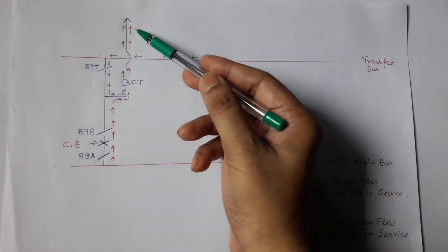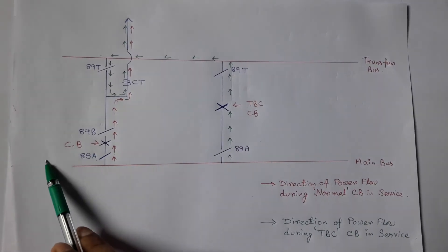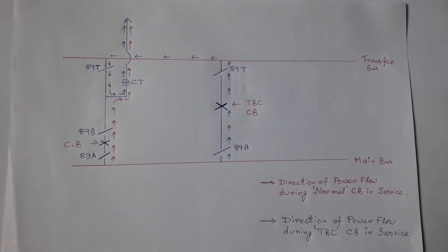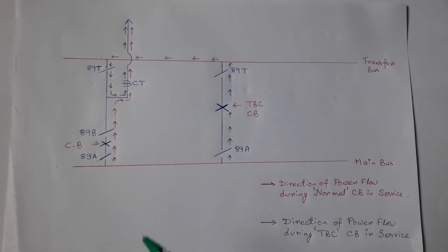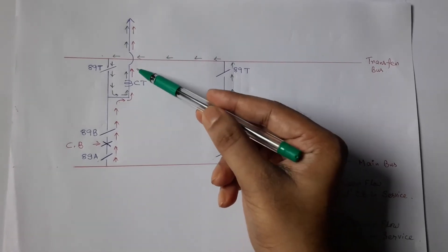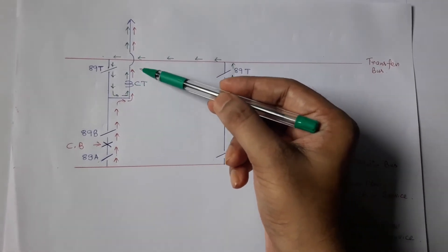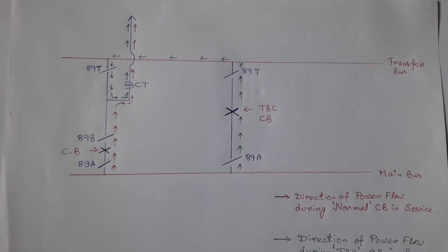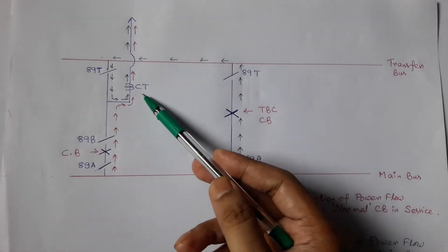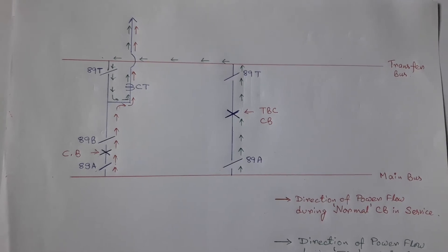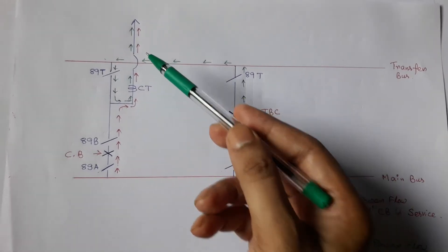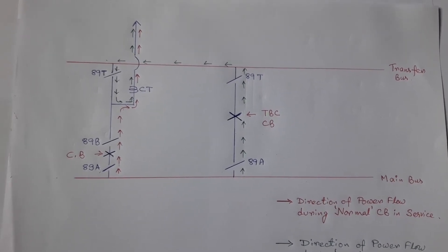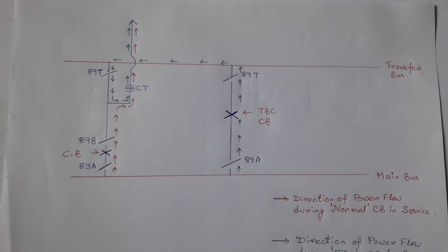But if any defect occurs in the normal circuit breaker, then the load of this feeder is diverted to the TBC circuit breaker, and the direction of power flow is shown in green. So to feed power to this feeder, we can use the normal circuit breaker or the TBC circuit breaker. Notice that for both cases, current is flowing through the same CT, and this type of CT is called a line side CT. For both cases shown in red and green, this line side CT will be responsible for detecting any fault in the line and will provide tripping to either the normal circuit breaker or the TBC circuit breaker.